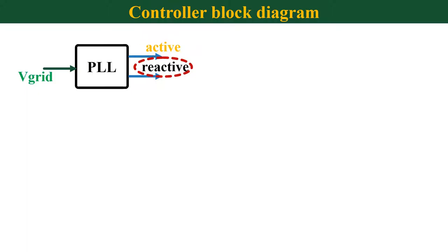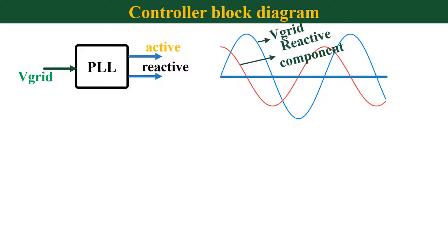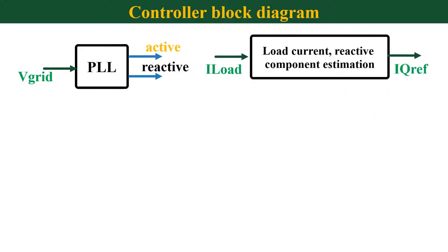Now I will explain the controller block diagram of a single phase active rectifier. We start with phase locked loop. Output of phase locked loop will give one active component and one reactive component. The active component is aligned in phase with the grid. Reactive component is aligned 90 degrees out of phase with the grid. The next step is to find the amount of reactive current present in the load. This current decides the amount of current the Statcom has to be generated. I will explain this in detail in the coming slide.